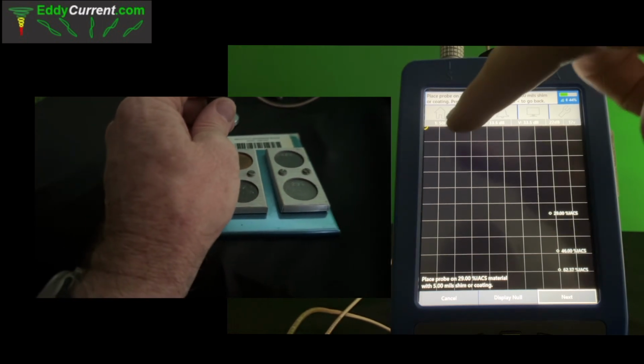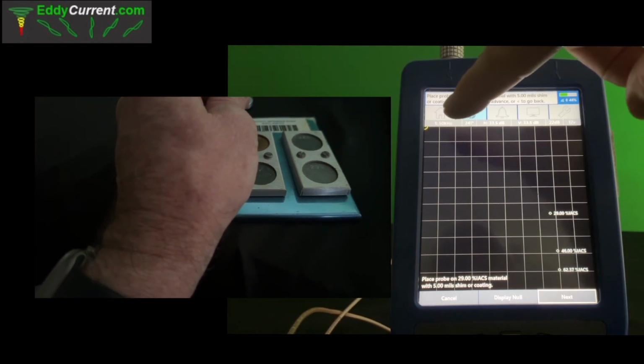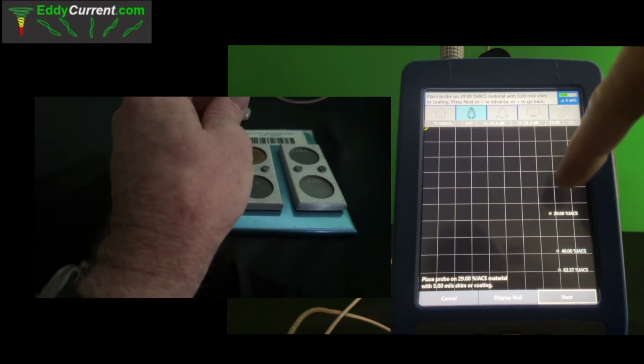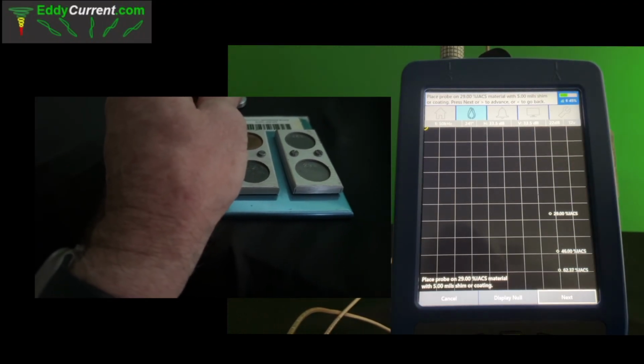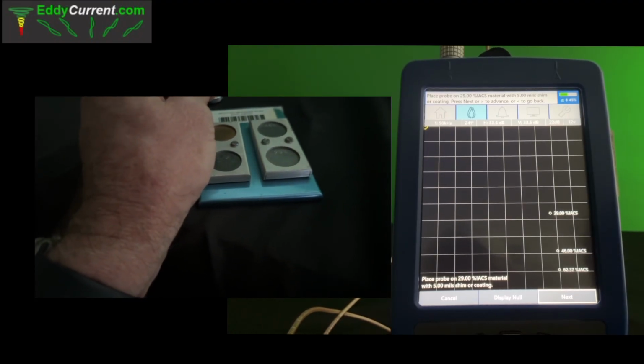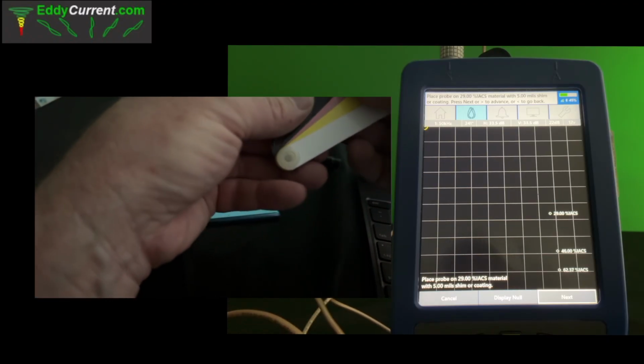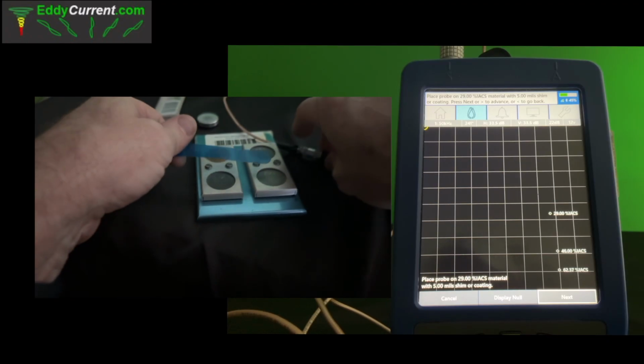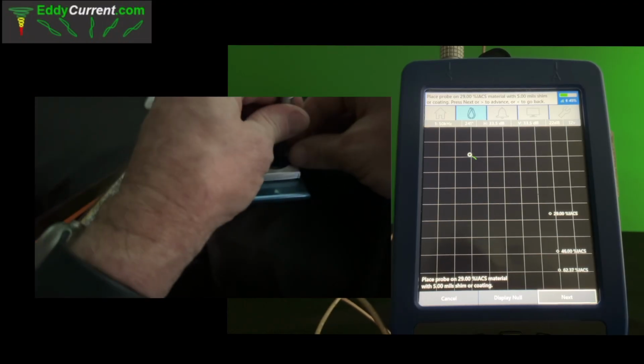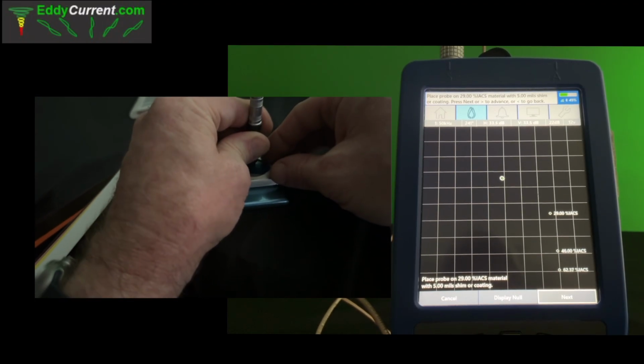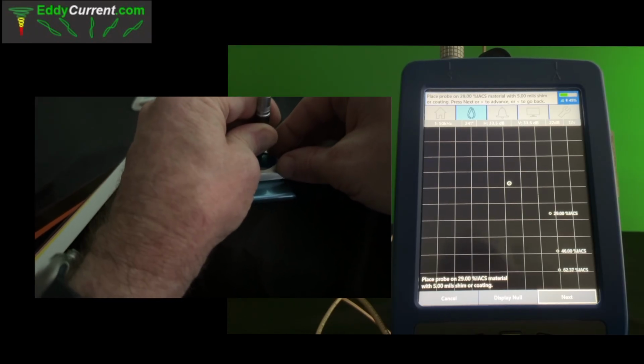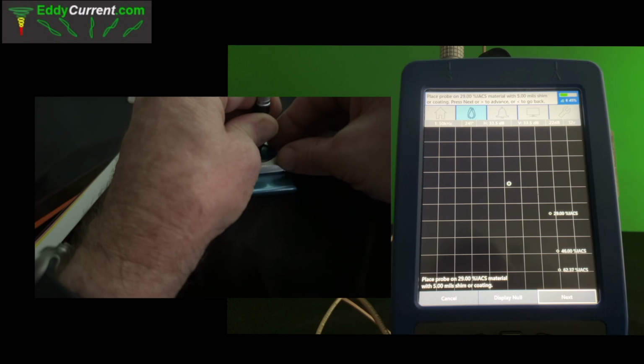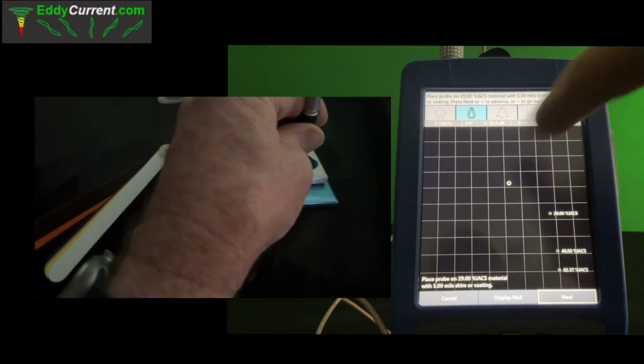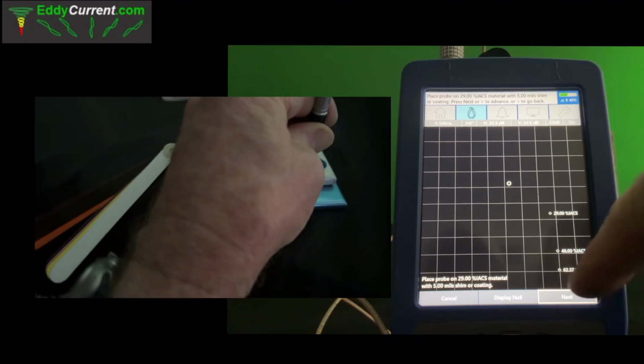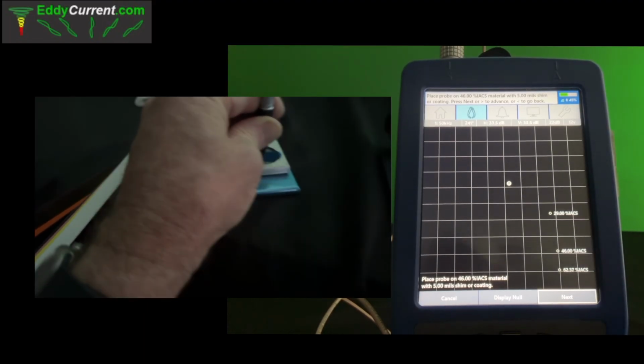So you can see the vector point of the unloaded coil in the upper left hand part of your screen. And the conductivity values fell right where you'd expect them to fall, with the highest conductivity being at the bottom. So now it wants us to use the 5 mil shim. And the 5 mil shim is blue. So we're going to put that on our first value. And watch the vector point and make sure that it makes sense on the impedance plane before you hit next. Because if that's in an obscure spot where it's not supposed to be and you hit next, you're going to have a messed up curve. But that position looks good.